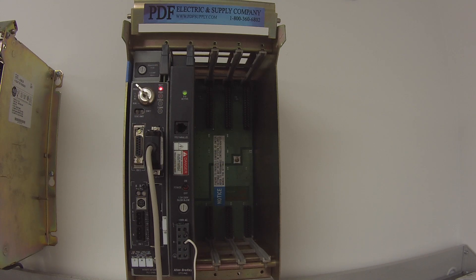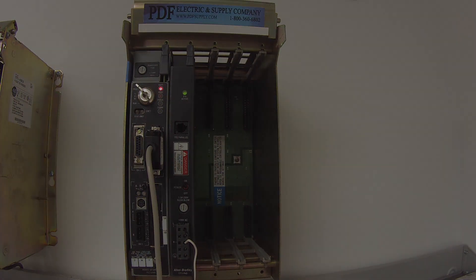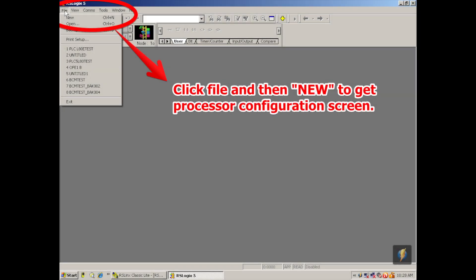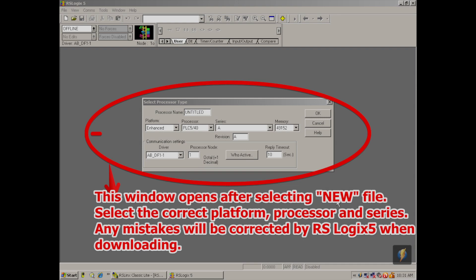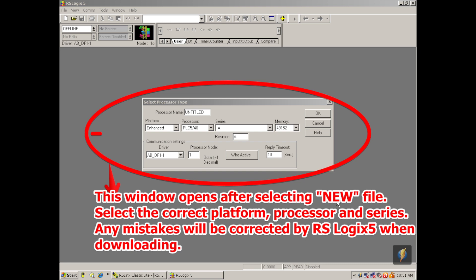Now I'm going to open up RSLogix 5 software, go to file, new, and a window is going to pop open asking us to select the processor type. So the platform is going to be ethernet. You want to change that to ethernet in the drop down. In this particular case, it's a PLC-5/40E for ethernet, and we're going to hit okay.